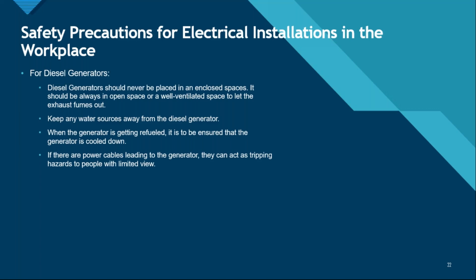Keep any water sources away from the diesel generator. In case the diesel generator is being refueled, it is to be ensured that the generator is cooled down before you refuel it. If it is not cooled down and you refuel the diesel into the generator, it might also lead to an explosion because of the heat and the fuel.